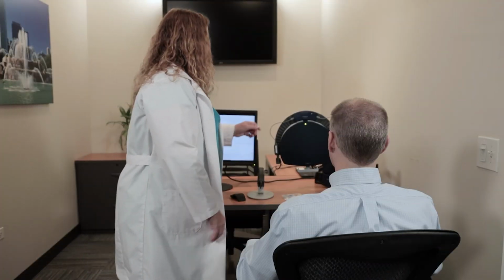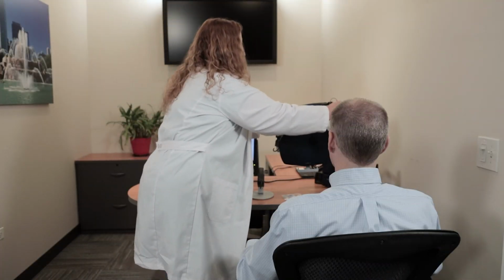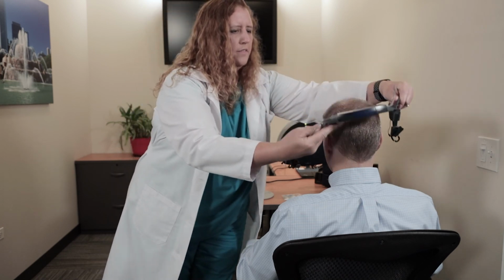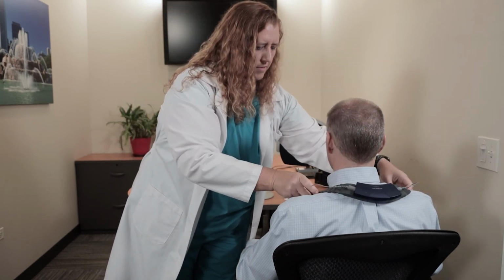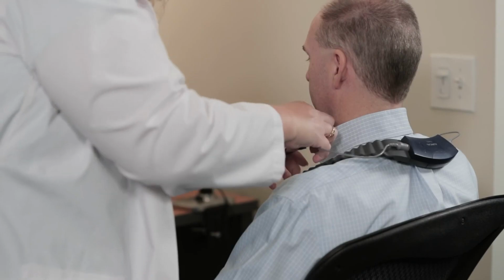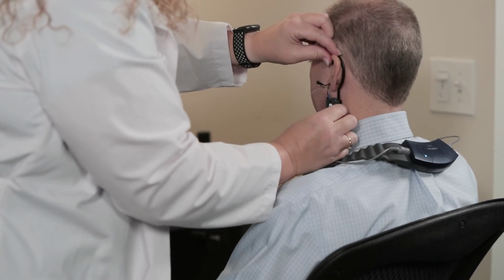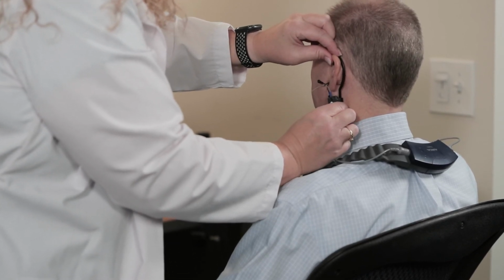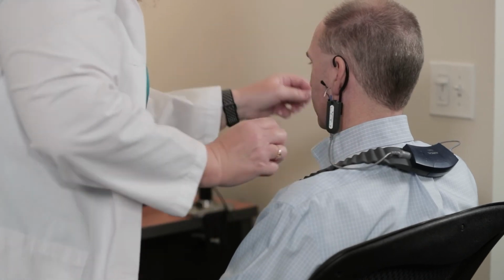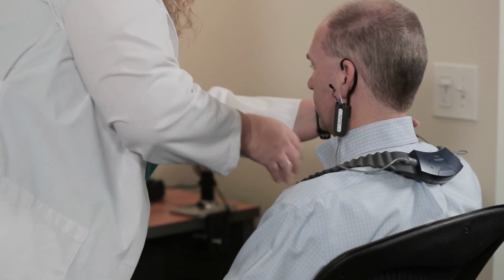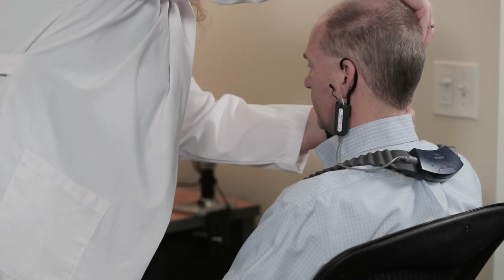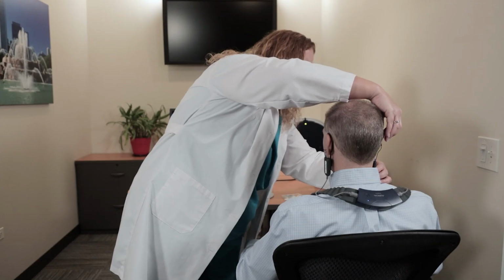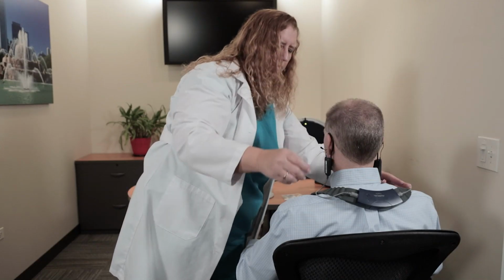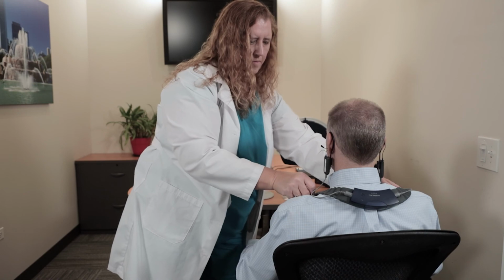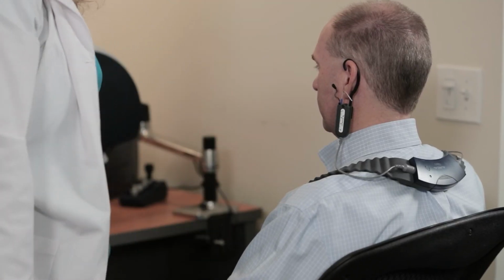If you've not done so already, place the free fit collar around the client's neck. Then place the ear loops or ear hooks over the client's ears, adjusting the length if necessary. Now that your Aurical PMM system is set up and the room and probe tube calibrations are complete, you are ready to begin the basic steps of verification: unaided response, occluded response, and aided response, which will be covered in the next 2 videos.